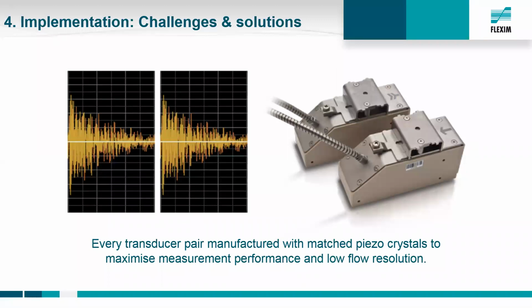So how we can ensure such competitive uncertainties, especially for transducers. We are using a method called wedding. So we take the core part of each transducer. It's the piezo crystal, and each piezo crystal has slightly different electronic characteristics, and these characteristics we determine on a bigger batch of crystals, and then we match each piezo crystal with the one matching it best, and so we can ensure or maximize the measurement performance and also the low flow resolution.